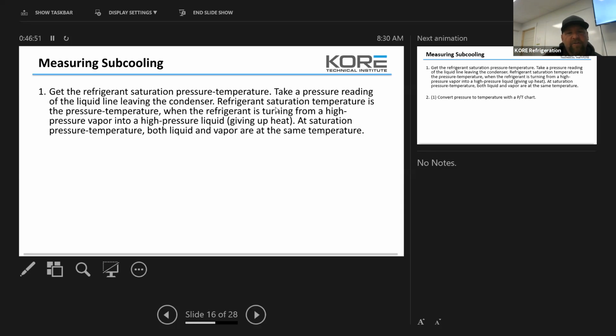So get the refrigerant saturated pressure temperature, take the pressure reading of the liquid line leaving the condenser. Refrigerant saturation temperature is the pressure temperature when the refrigerant is turning from a high pressure vapor into a high pressure liquid, giving up heat at saturation pressure temperature. Both liquid and vapor are at the same temperature. Okay.